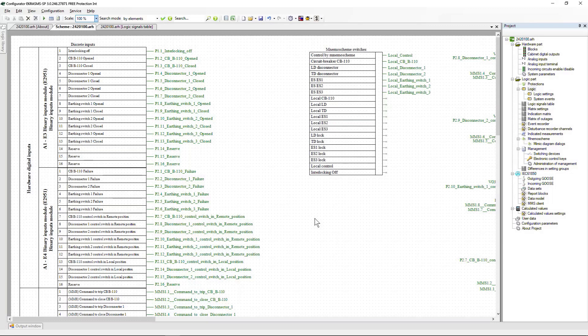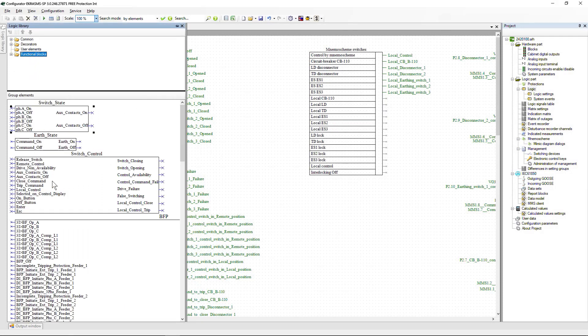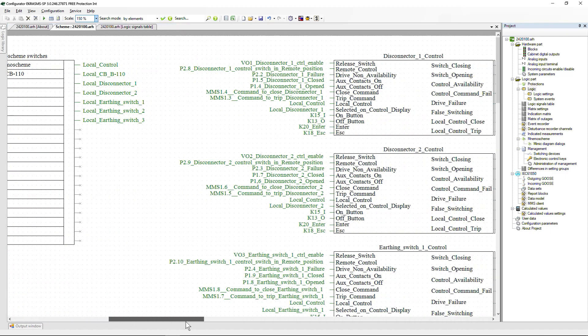The ED2 devices provide the possibility of controlling switching devices remotely and from the mimic diagram of the IED. For this purpose, the IED logic provides the functional unit Control of Switching Device, which can be added by dragging and dropping from the library in the Functional Units folder. This functional unit implements controlling the switching device from the mimic diagram, remote control from the upper level PCS over digital communication channels, blocking control in case of drive failures, and diagnostics for incorrect command execution. Each switching device requires its own functional control unit.